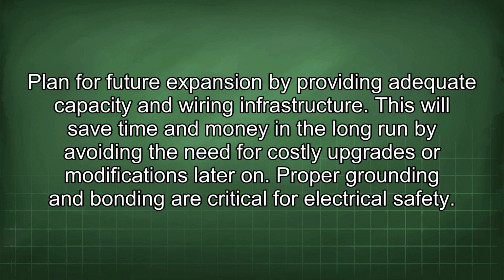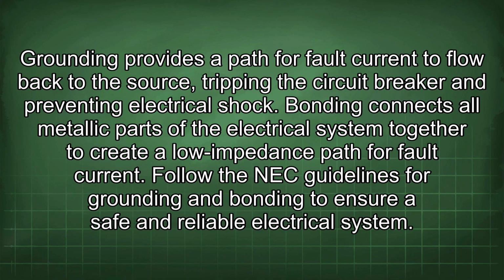Proper grounding and bonding are critical for electrical safety. Grounding provides a path for fault current to flow back to the source, tripping the circuit breaker and preventing electrical shock. Bonding connects all metallic parts of the electrical system together to create a low impedance path for fault current. Follow the NEC guidelines for grounding and bonding to ensure a safe and reliable electrical system.